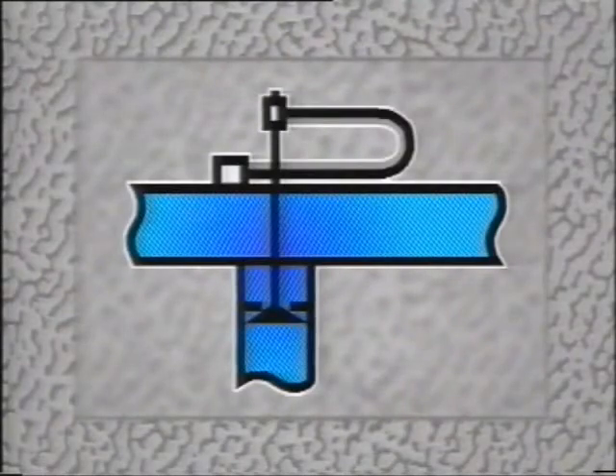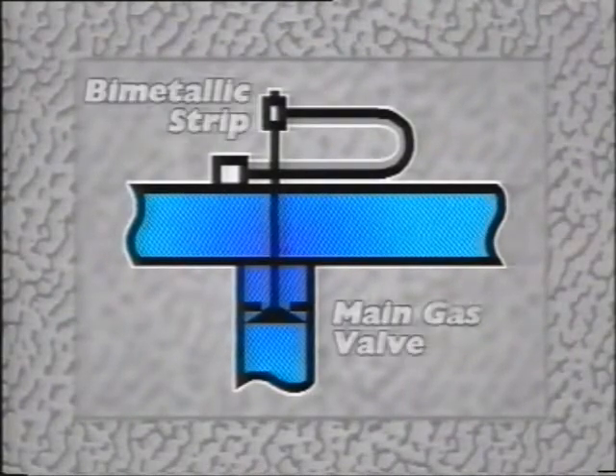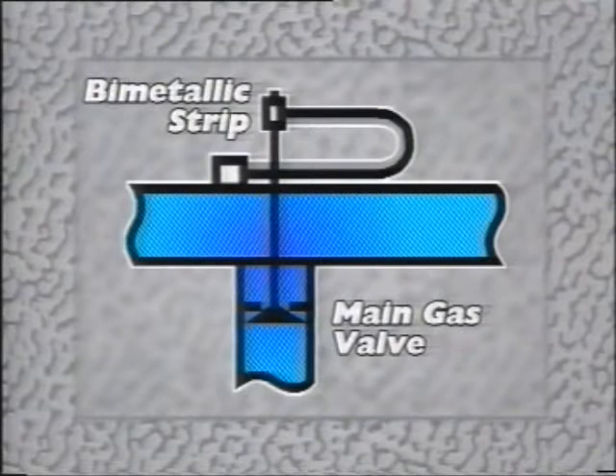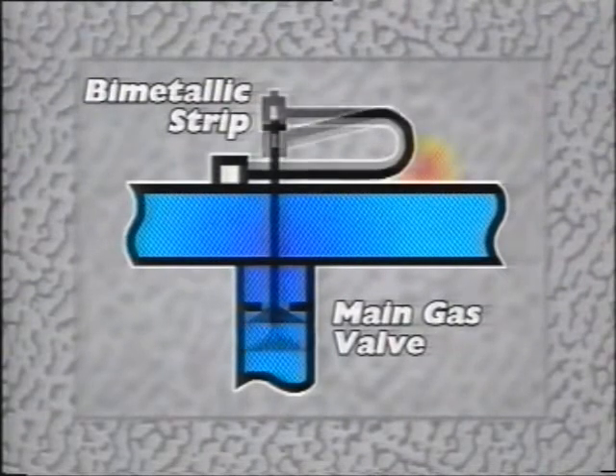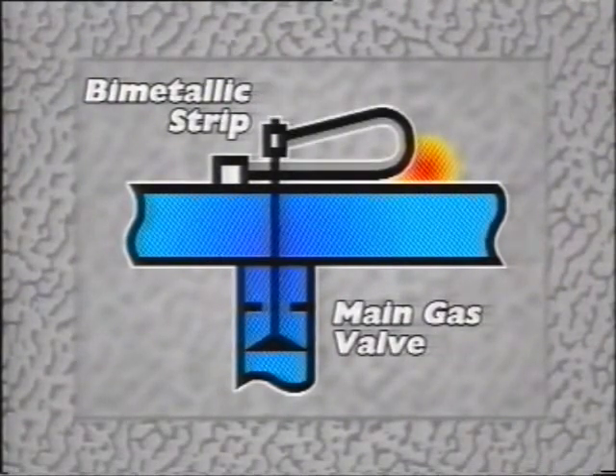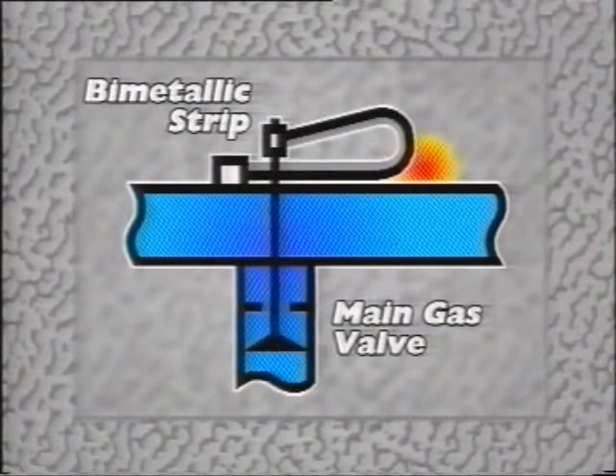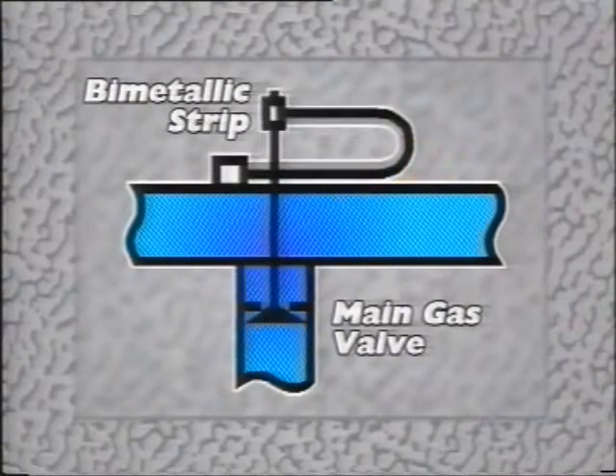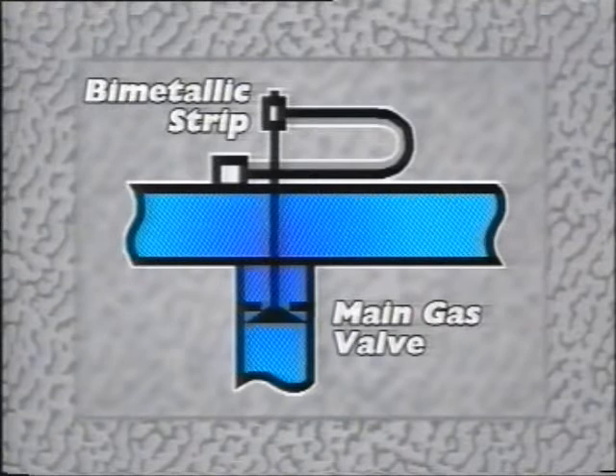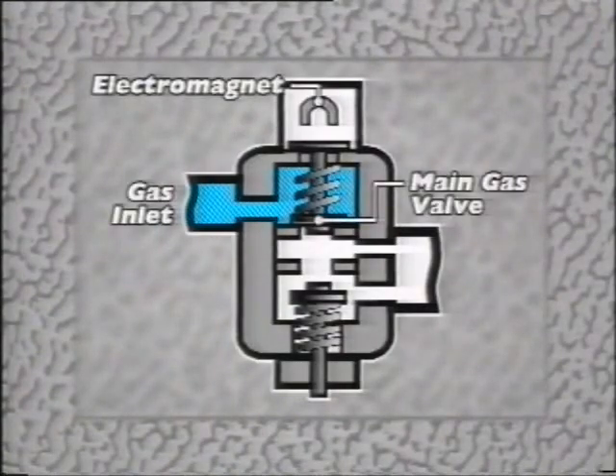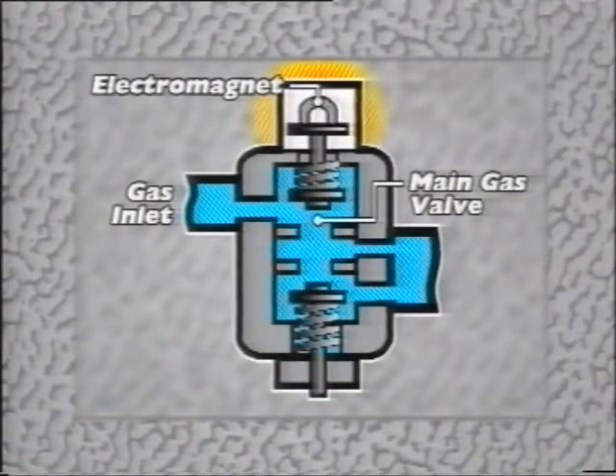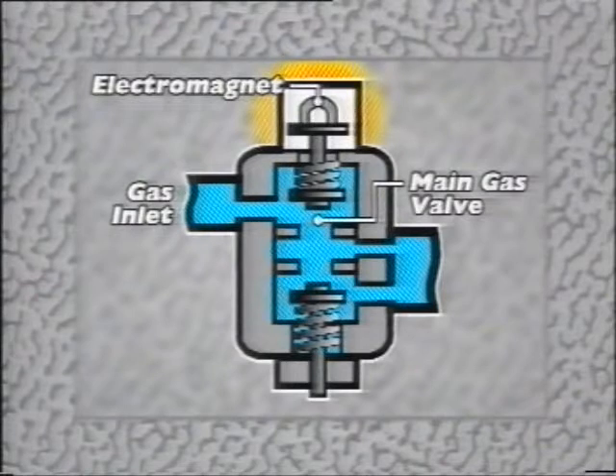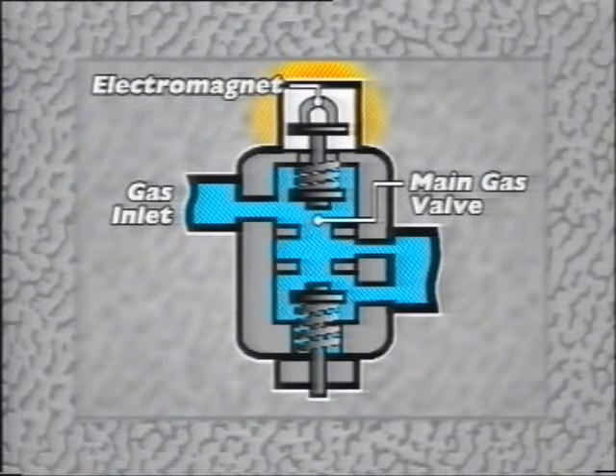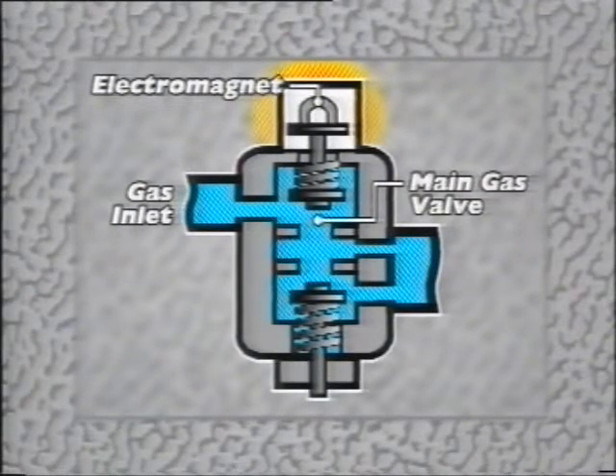The flame safety device is a bimetallic strip. When it's heated by the pilot light, it bends and opens the main gas valve. If the pilot or gas goes out, the strip returns to its natural shape and closes the valve. Today, it's being replaced by a thermoelectric valve. When dissimilar metals are heated by a pilot light, they produce an electrical current, which creates an electromagnetic effect. This holds the main gas valve open.